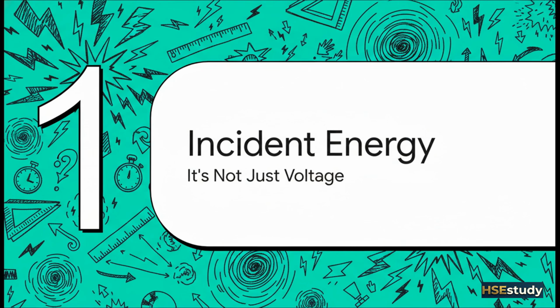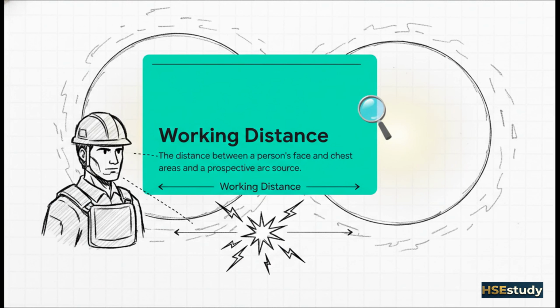All right, so the heart of this whole thing isn't the voltage, it's the incident energy. That's the real measure of the hazard, right? It's the thermal energy, measured in calories, that's going to hit your body. And that energy is really governed by two key variables that are, frankly, dangerously misunderstood, especially in low-voltage work: distance and time. So let's talk about variable number one, working distance.